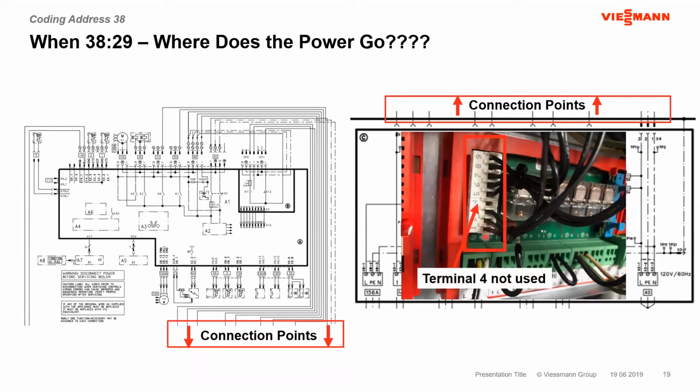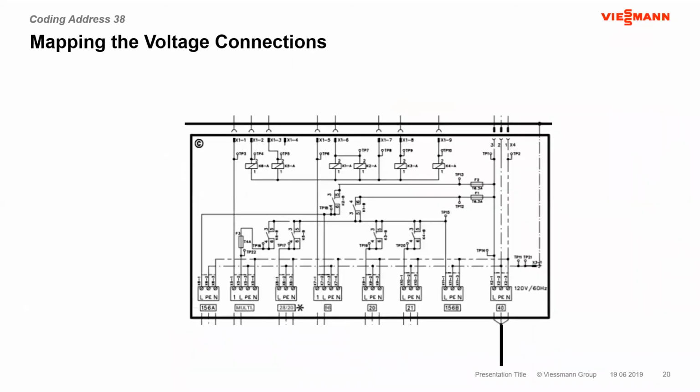But there's the connection between the pump module and the control console that sits above it, are all at these points here. Great testing points to look for different voltages and stuff like that, as there should be specific events that happen to make those relay coils energize and close the contact. So good points here to test, and those are what we're going to review here as we move through.